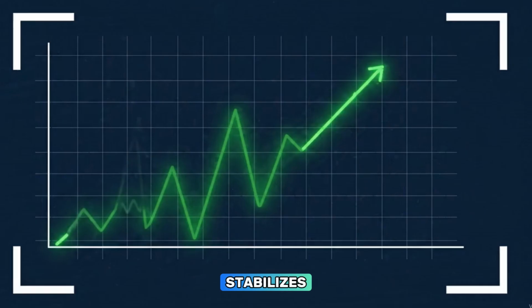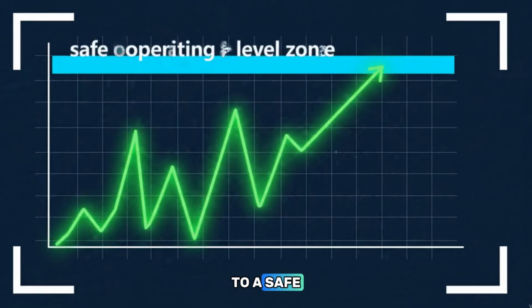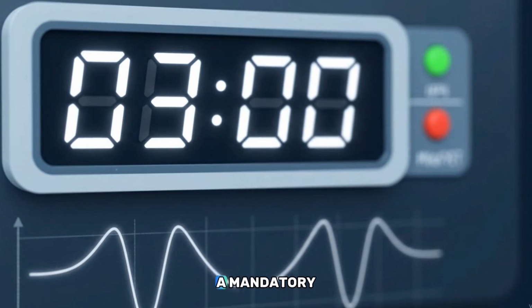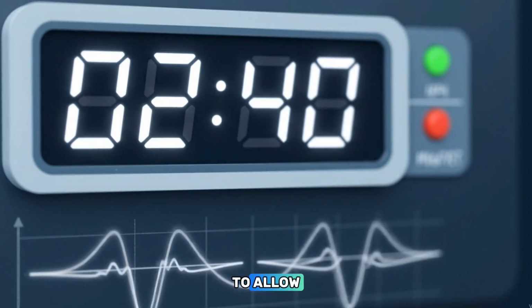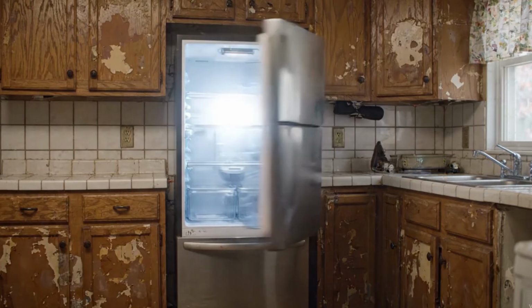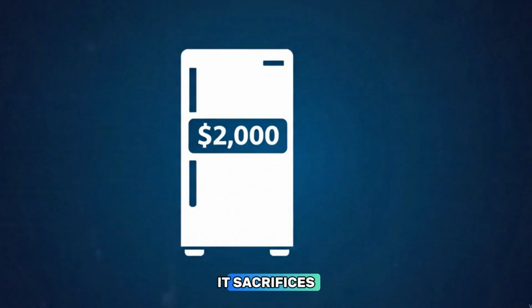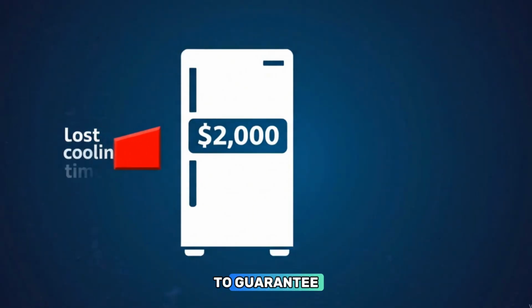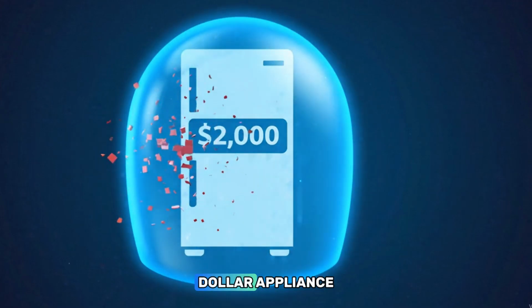Once the grid stabilizes and the voltage returns to a safe operating level, the relay waits a mandatory 3-minute delay to allow refrigerant pressures to equalize and then restores power. It sacrifices a few minutes of cooling to guarantee the survival of a $2,000 appliance.